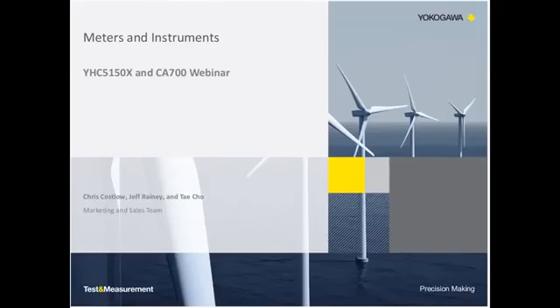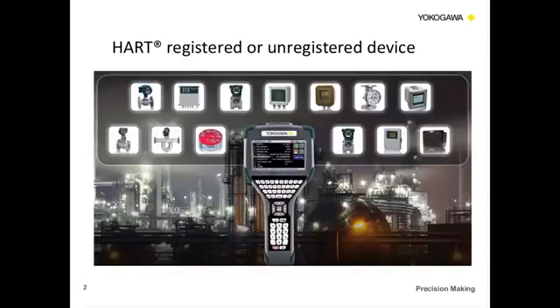The first product we're going to discuss is the YHC5150X, the Fieldmate handheld communicator. One thing I want to point out before we get started is the YHC works with all manufacturers' devices that have the HART protocol. We definitely want you to use Yokogawa products such as the flow meters and transmitters and other devices, but this works with every other manufacturer's products as well, their flow meters, pressure transmitters, and temperature transmitters, if they have the HART protocol.